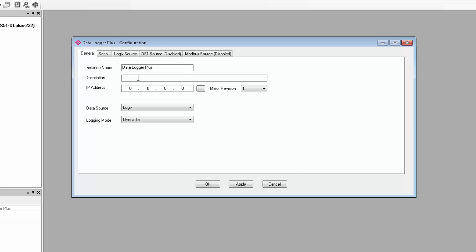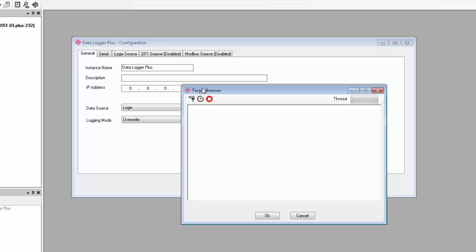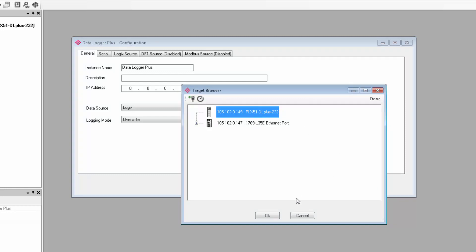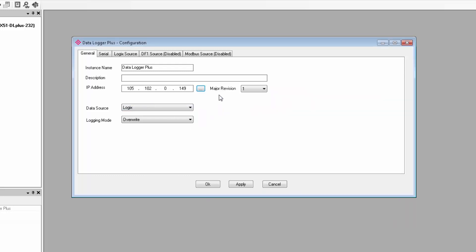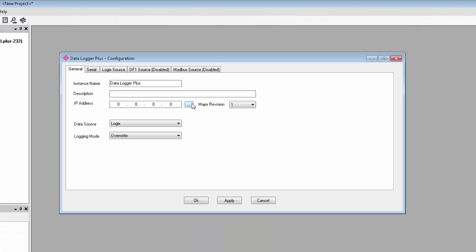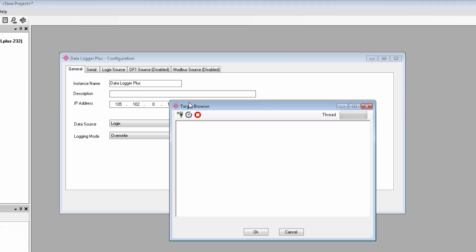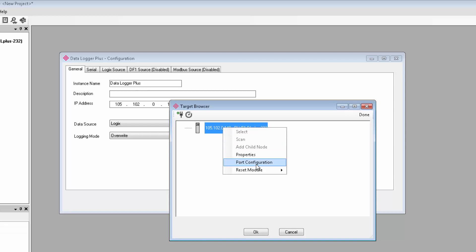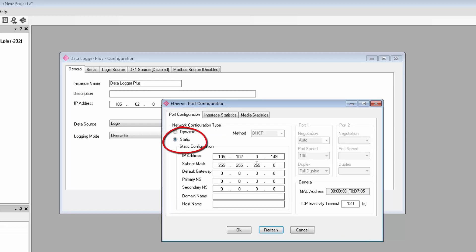So on the general tab, you give the gateway an instance name and a description, if you like. You then enter the IP address. You can either type in the address manually or you can click the Browse button to the right of the field to bring up the target browser where you can see all the devices on your network and just select your PLX51 module. This will be the address that you use to access the module and it'll be the address that you just assigned to it a minute ago. If you already have a DHCP server on the same subnet as the IP that you want to assign the module, you can just let it assign an address to the data logger plus. Then, simply right-click the data logger plus here in the target browser and select port configuration to set a static address.